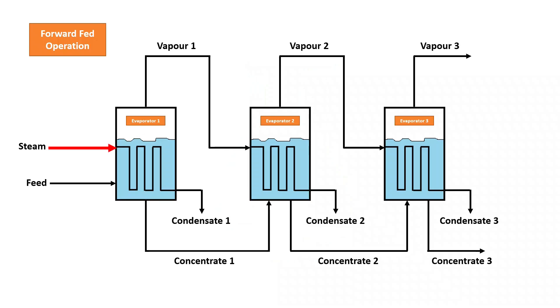Hot steam is passed through metal tubes within the evaporator and leaves as condensate. The cold feed solution is pumped into the first evaporator and makes contact with the hot metal tubes, which heats the solution and causes some of it to vaporize.